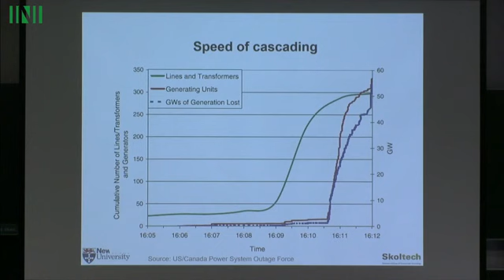So this is lines failing, and this is the generators failing, because as frequency drops, voltages go down, then power stations start to fail as well because of the equipment. That gives you an example of how important it is to have automatics in place, because once you get over here, there's no way of stopping it. So you have to prevent it from happening.